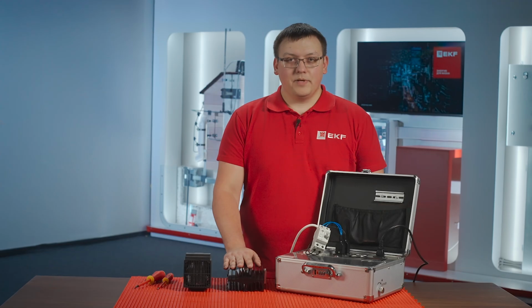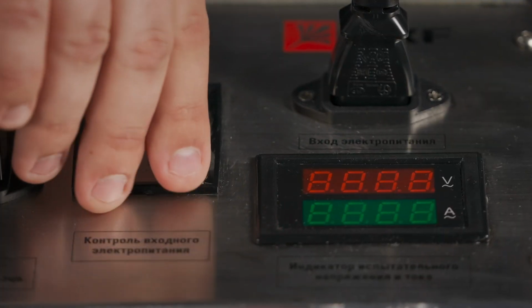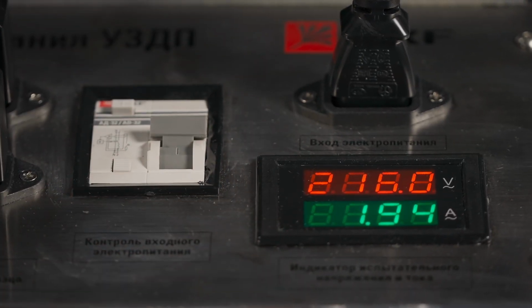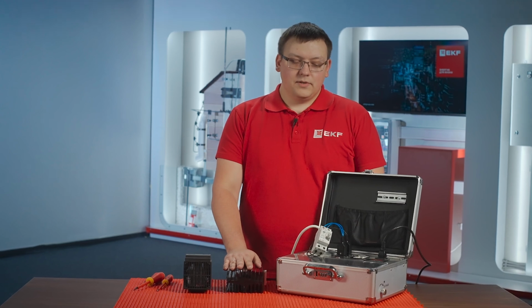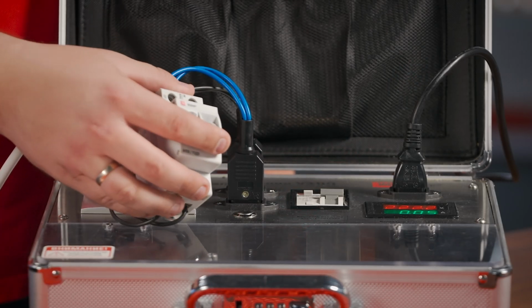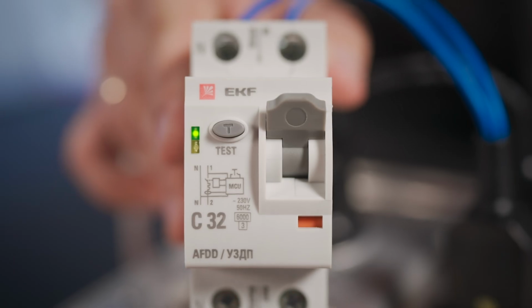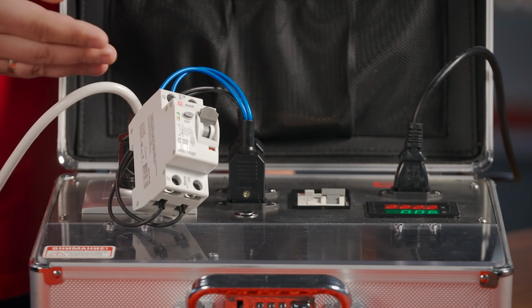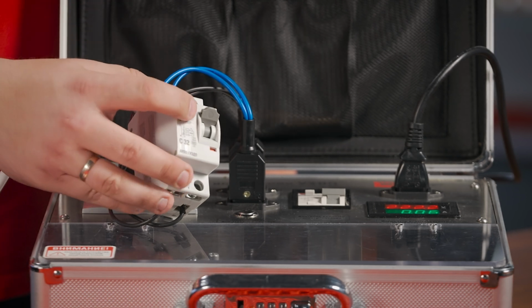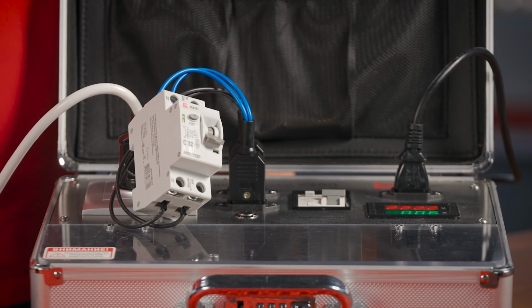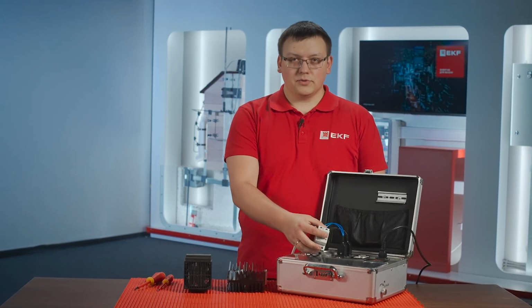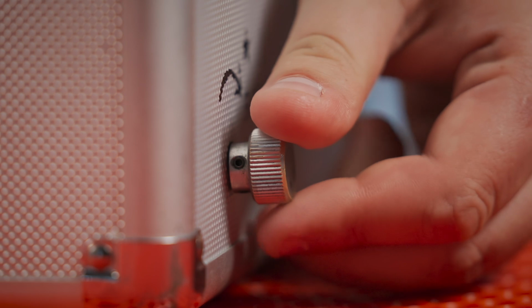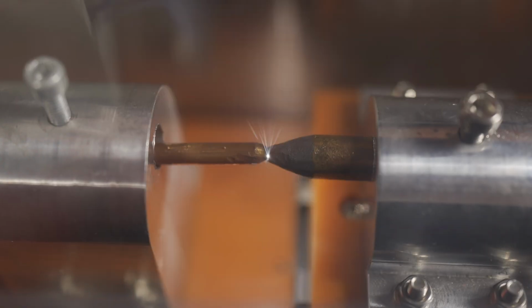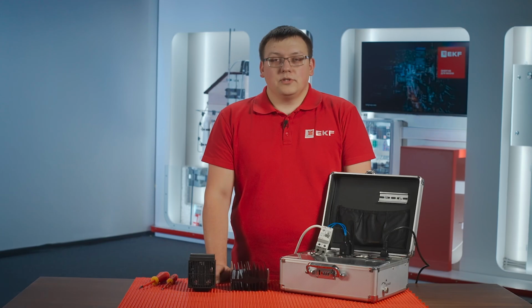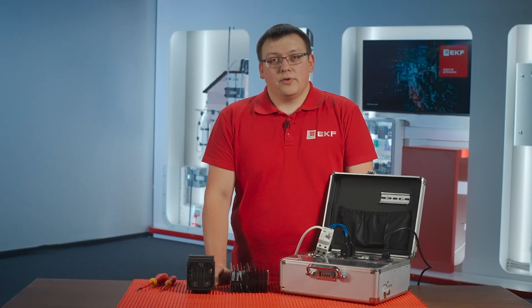Let's start the test. We energize the circuit by switching the 32 amp input RCBO. The digital voltmeter shows 220 volts and no current draw. Now we switch on the arc fault detection device. Notice that the green LED is glowing. This means that AFDD is OK and it's working. Press the test button to see if it triggers. Rearm the AFDD again. Now, we gradually increase the distance between the carbon rods to generate an arc. AFDD had triggered at 2.5 amps, which is within regulatory requirements.